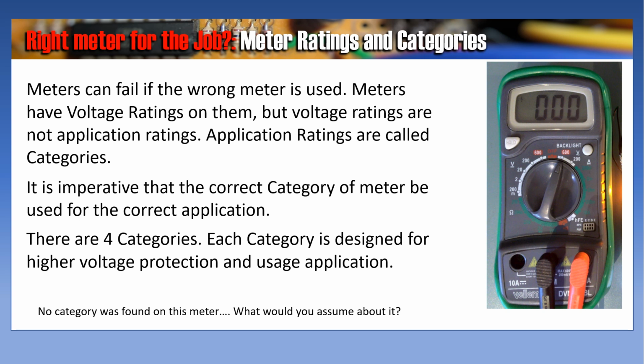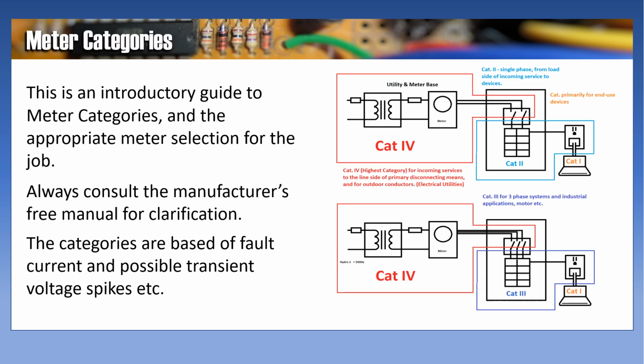There are 4 categories. Each category is designed for higher voltage protection and usage application. On the meter shown, there's no category found. What would you assume about this meter? Well, let's find out. To be clear, this is just an introductory guide to meter categories and the appropriate meter selection for the job. Always consult the manufacturer's free manual for clarification. These categories are based on the fault current and possible transient voltage spikes, etc. for each category.